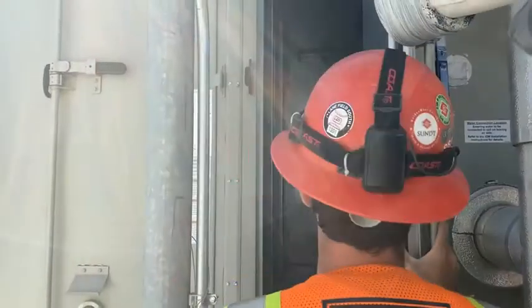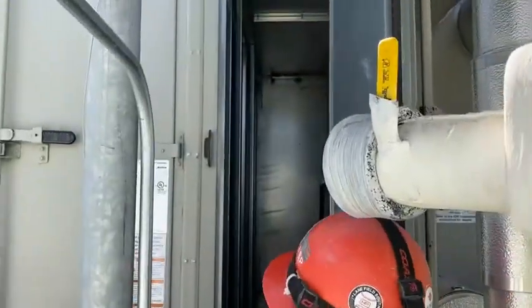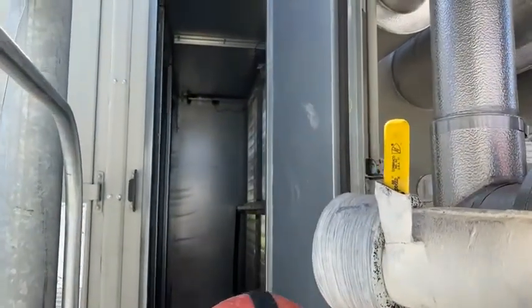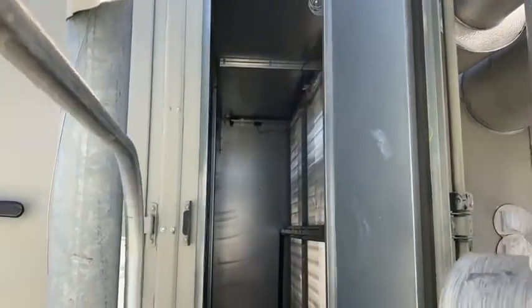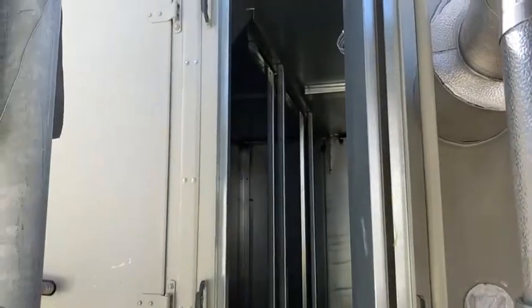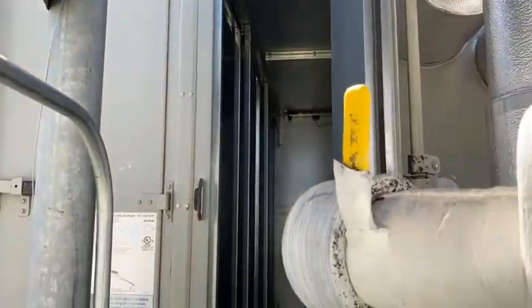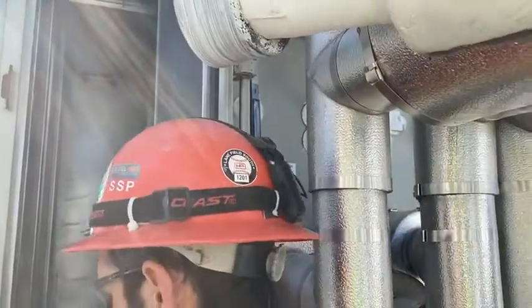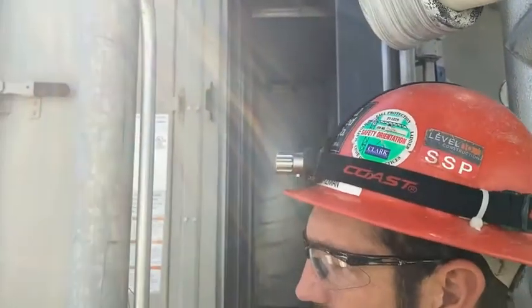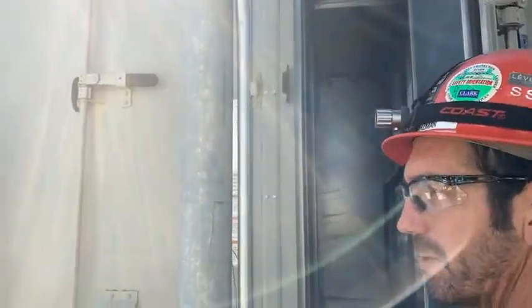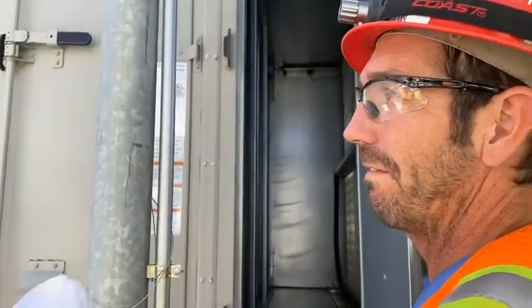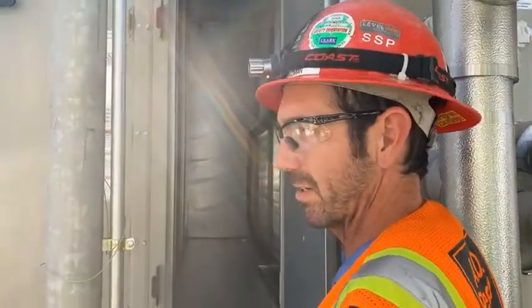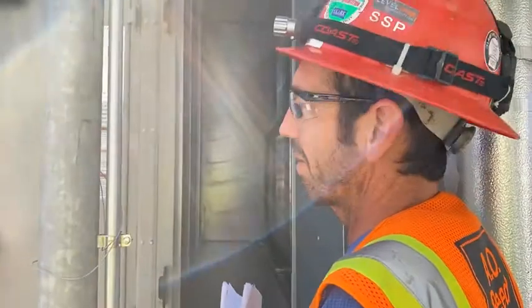It's going to be the coils and the inlet to the fan. You got multiple fans? Yeah, there's going to be 2 fans in this unit right here. So this is a fan wall application, a 2-wall fan wall. Okay. In a fan wall application, we can run the motors faster than 60 hertz. On the pumps, we stop at 60 hertz. On fan walls only in air handling units, you could run the motors over 60 hertz with the VFDs, and I'll go over that when we talk about that compartment, okay?